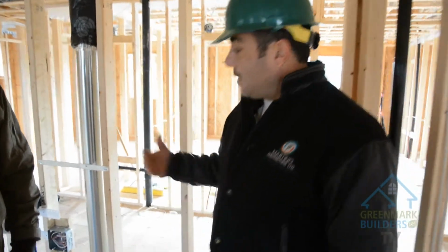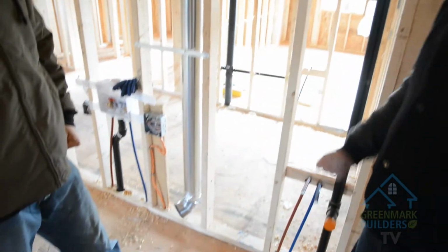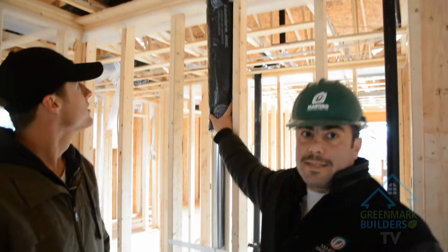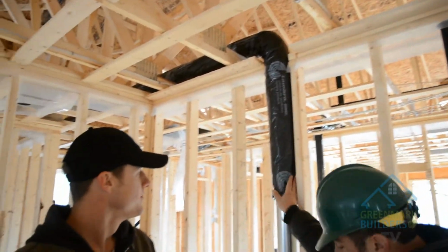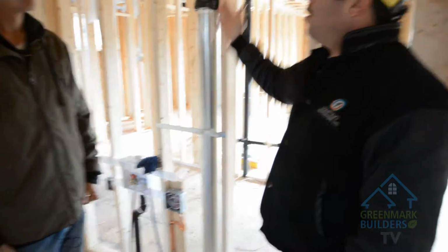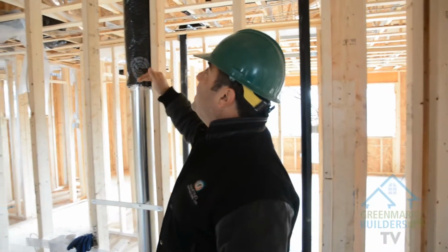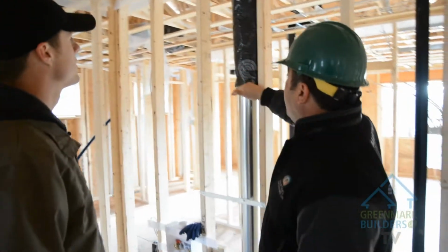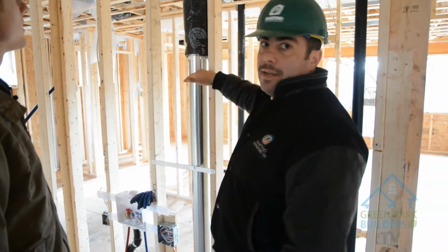Also, for exhausting outside, it's very important to have insulated flex on the rigid pipe. For example, we have a dryer here going into the attic, so you want to make sure it's insulated all the way through the attic, and also for the first 4 feet inside the wall, to keep the moisture down. Cold air and warm air mixing creates moisture, and then you'll get damage in the drywall when it's finished. So keep the humidity basically controlled.